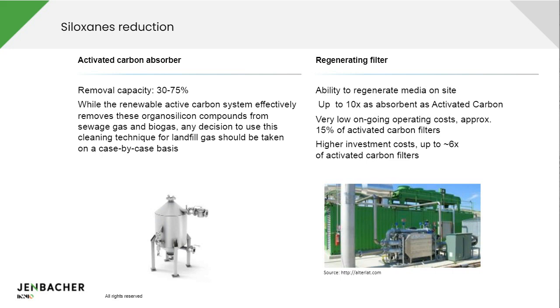Let's see, the issue with the activated carbon absorber obviously is that once the media, the carbon, is saturated, then you have to replace it. So there's a higher cost of operation in a sense, especially if you have very high quantities of siloxanes. But the cost of such an absorber is, let's say, relatively reasonable.